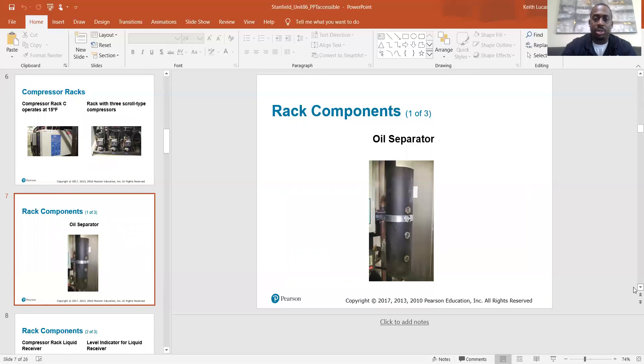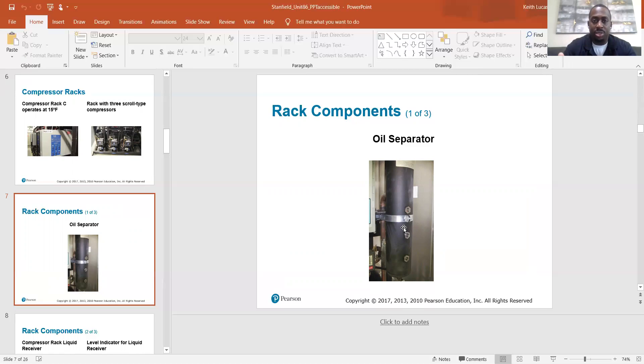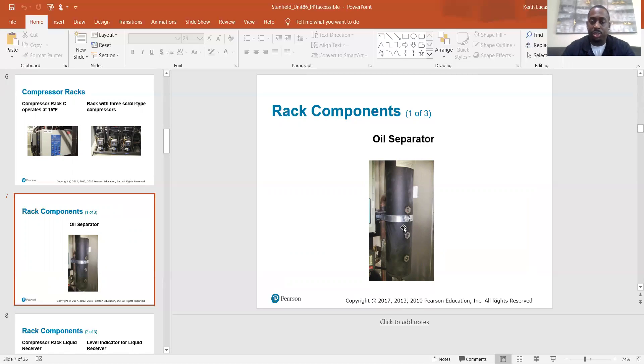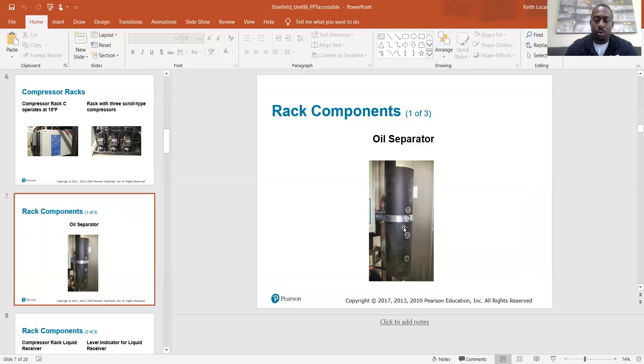So rack components. One of the components is your oil separator. As we know, the oil separator is located in the discharge line and it separates the oil from the refrigerant. So out of the top of the oil separator, the discharge gas can travel from there on to your condenser and then out of the bottom of the oil separator, it's returning the oil to the compressor.